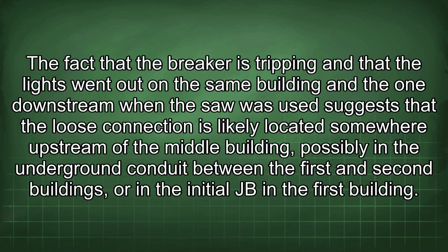The fact that the breaker is tripping and that the lights went out in the same building and the one downstream when the saw was used suggests that the loose connection is likely located somewhere upstream of the middle building, possibly in the underground conduit between the first and second buildings, or in the initial JB in the first building.